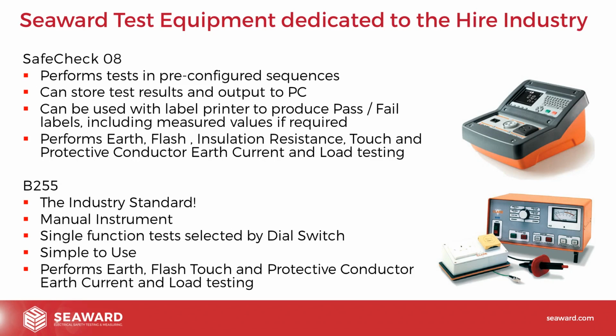Our other alternative, the workhorse, the industry standard as we like to call it, is the B255, a very simple, very well-known instrument in the hire industry. It's a single function test selected by a very big, easy to use dial. In this case, it performs earth testing, flash testing, protective conductor current, load testing and touch leakage testing. It doesn't perform the insulation resistance test, but you still have the protective conductor current and the touch current test as alternatives where you may not perform a flash test.